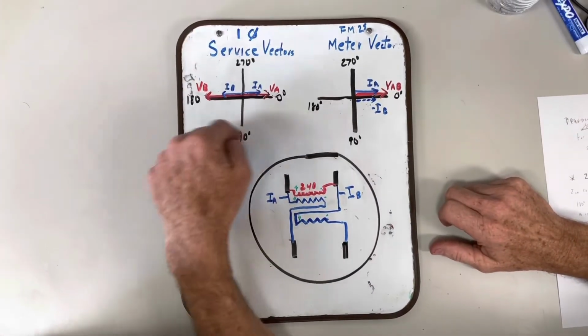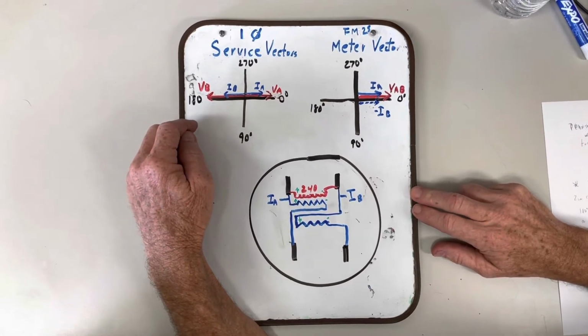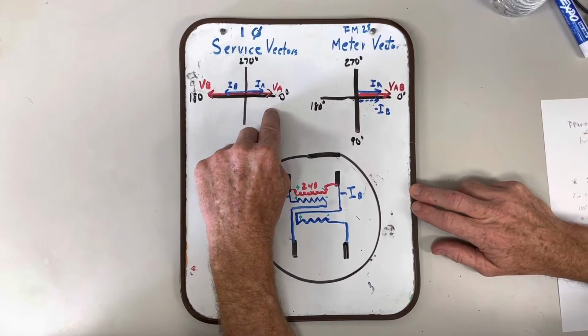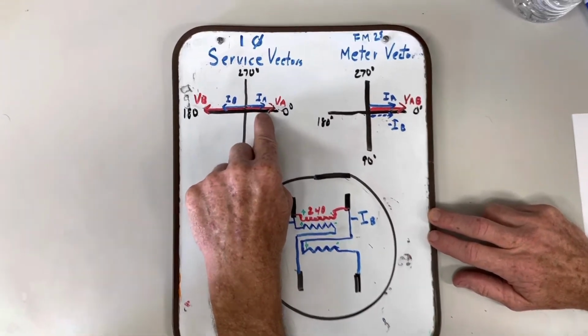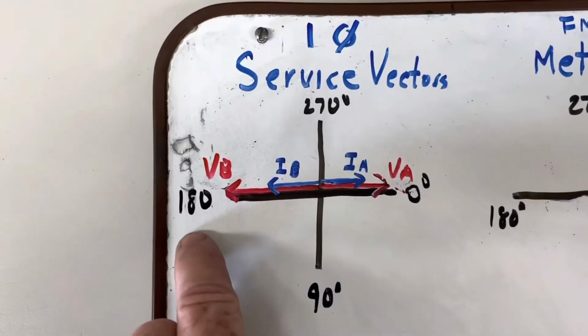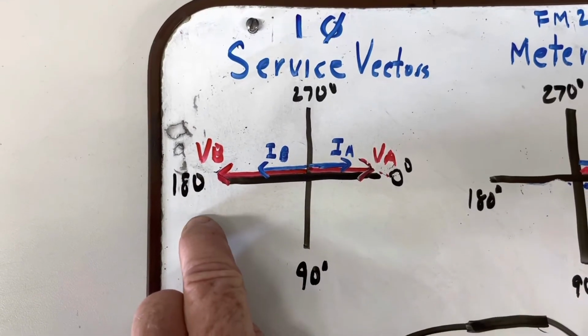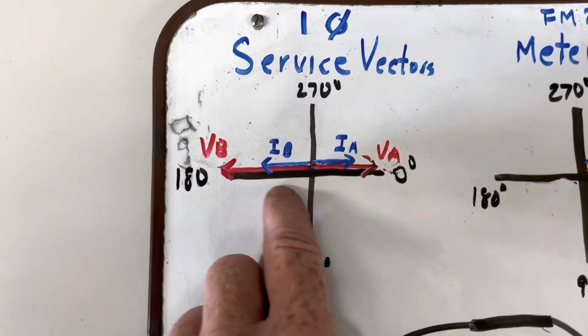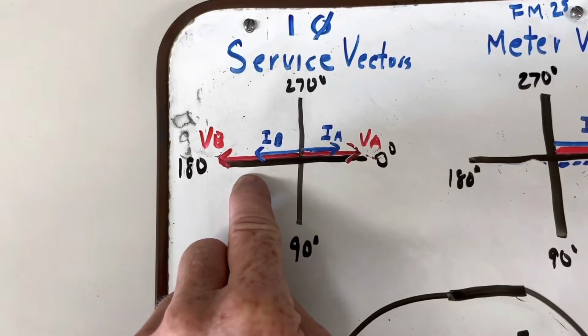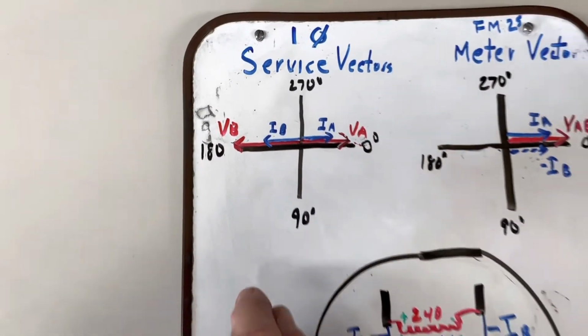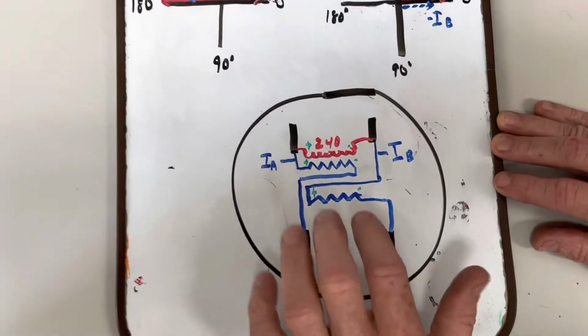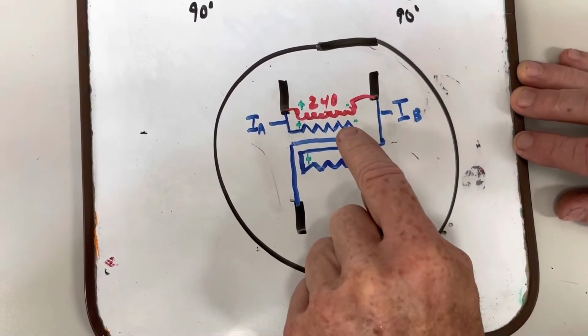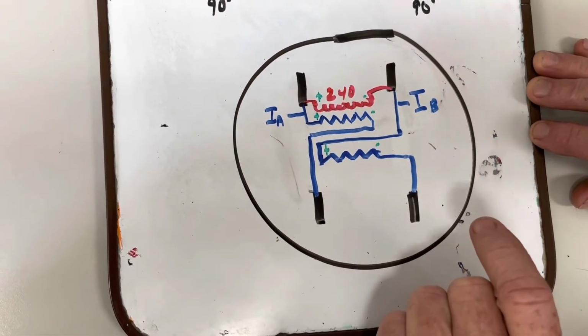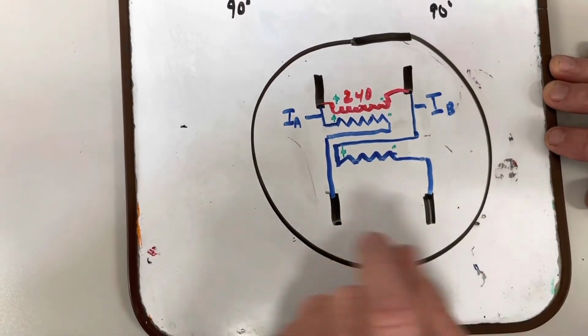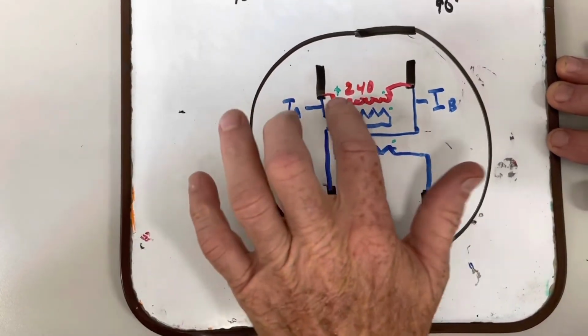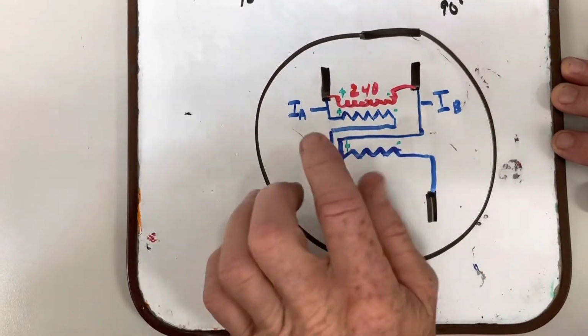Okay, we're gonna focus right here on the single phase service vectors. We have a voltage A at 0 degrees and unity current A at 0 degrees. We have voltage B at 180 degrees and current B at unity 180 degrees. To meter this service, we use Blondel's theorem N-1 because we're using 1 potential coil to meter 2 wire service, 2 wires. So on this particular meter, we have a 240 volt coil with 2 current coils.